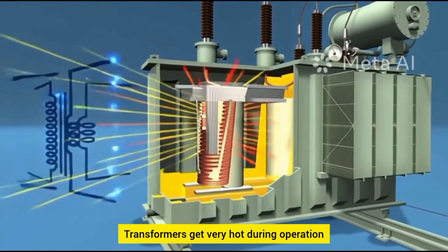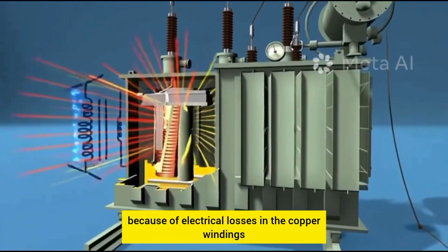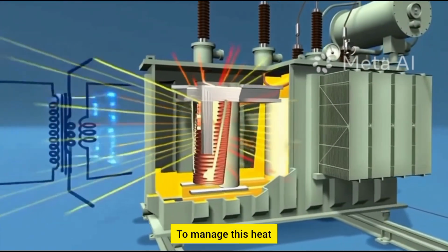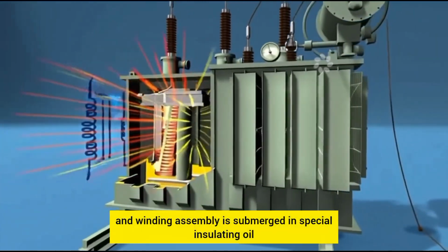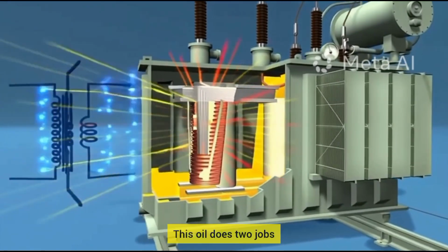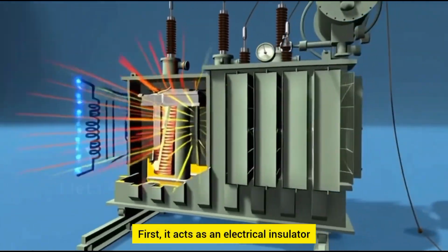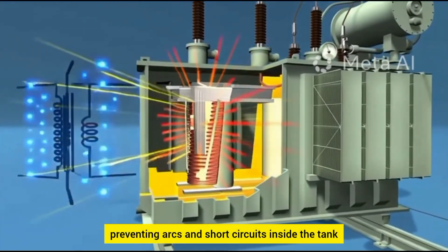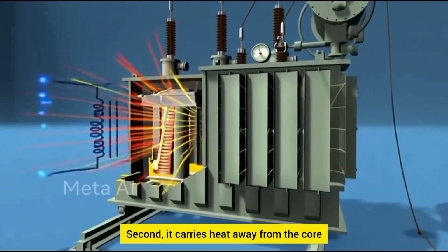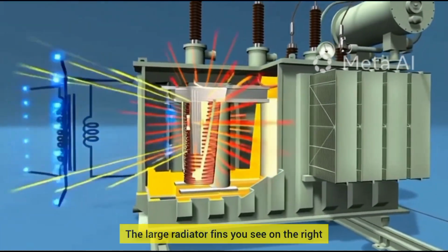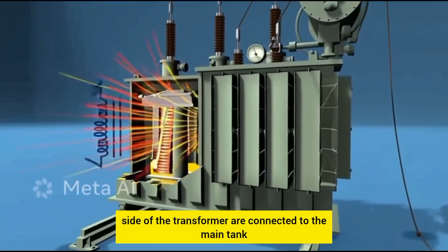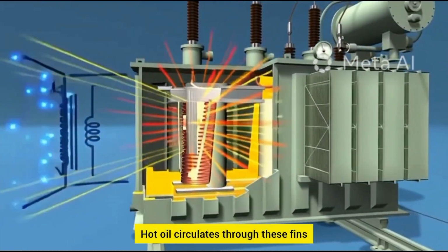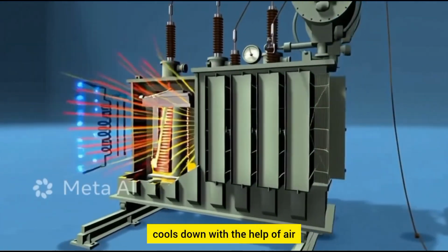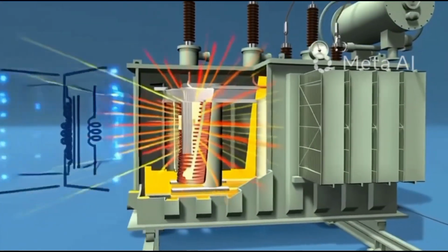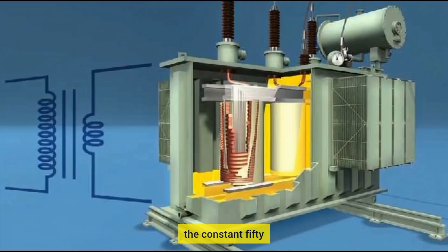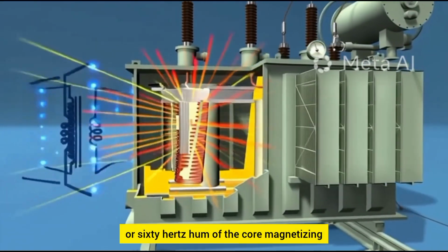Transformers get very hot during operation because of electrical losses in the copper windings and the iron core. To manage this heat, the entire core and winding assembly is submerged in special insulating oil. This oil does two jobs. First, it acts as an electrical insulator, preventing arcs and short circuits inside the tank. Second, it carries heat away from the core. The large radiator fins you see on the right side of the transformer are connected to the main tank. Hot oil circulates through these fins, cools down with the help of air, and then returns to the tank.